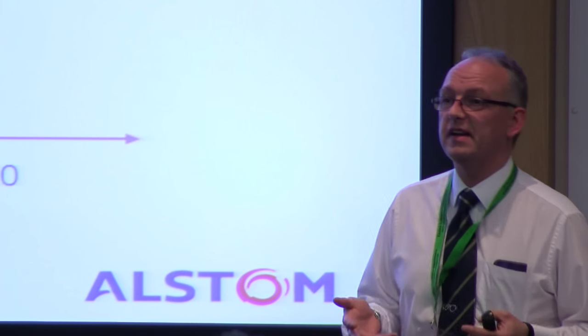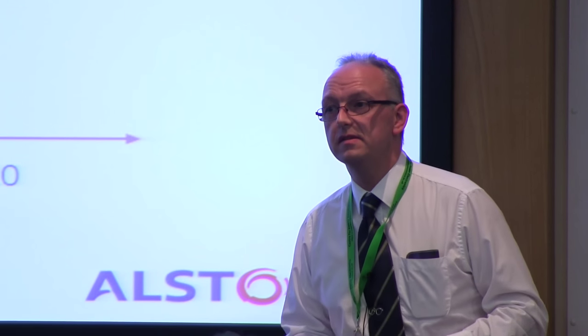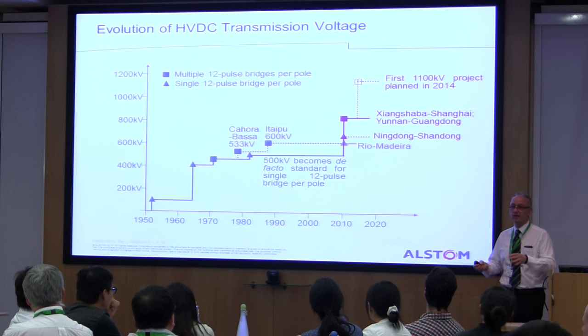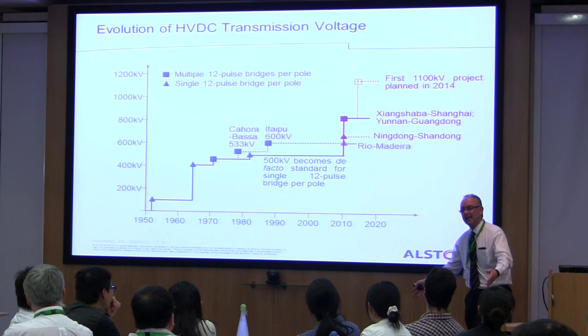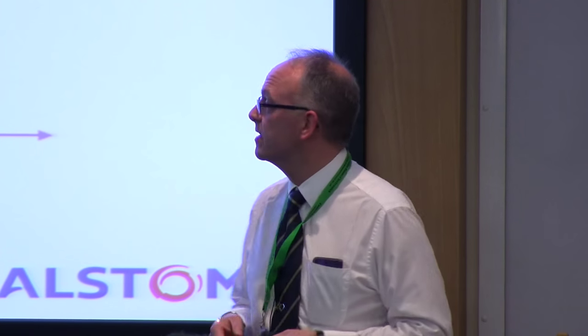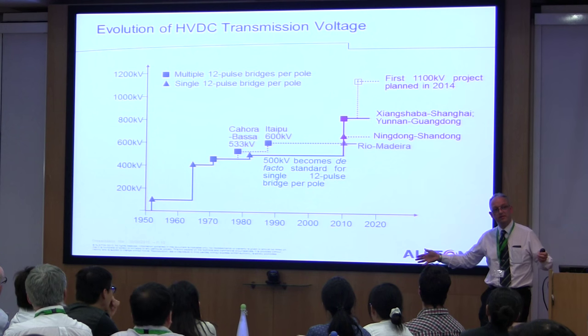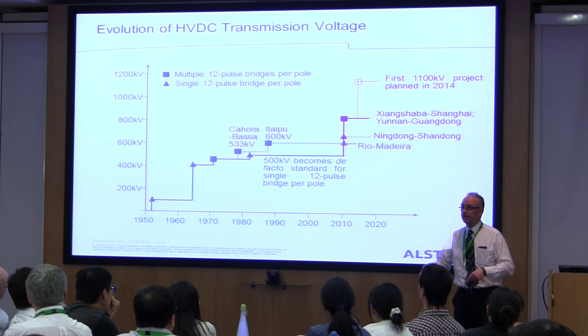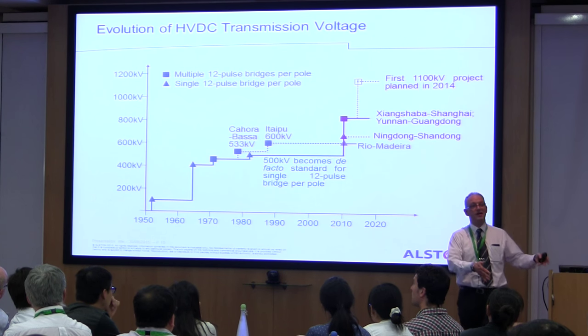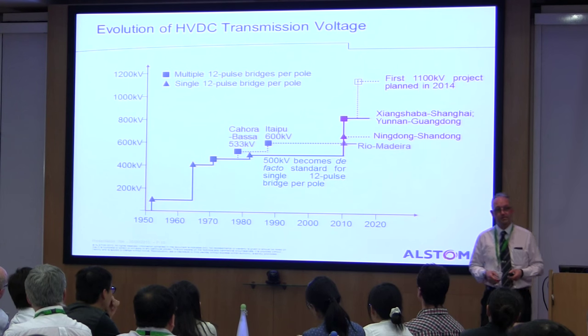When designing an HVDC scheme, the biggest thing you have to get to site is the transformer. Valves are easy to ship — they come in packing cases and you assemble them on site. The transformer is one big item, and it can very often influence your design. A bridge you have to go under limits the transformer height, forcing higher leakage reactance than you'd ideally want; a weight limit means you may not get the impedance you want. At 1100 kV they're talking about building the valve hall first and using it as an assembly plant for the transformers — shipping them in pieces, assembling on site, then populating the valve hall with valves. It's big.